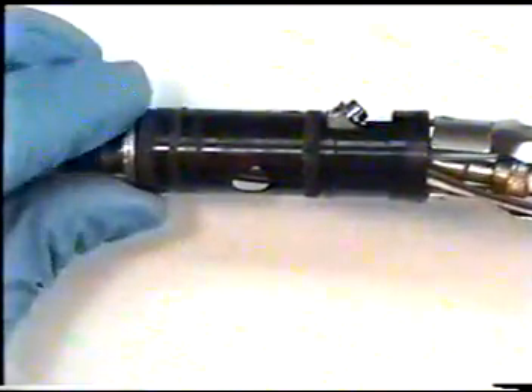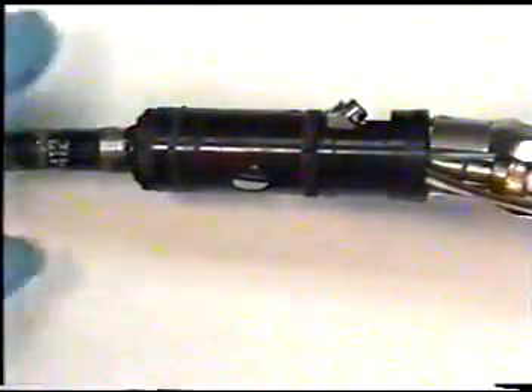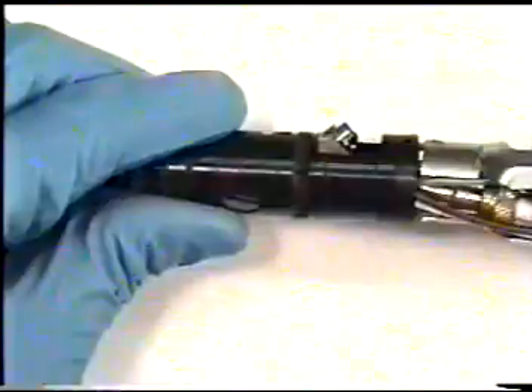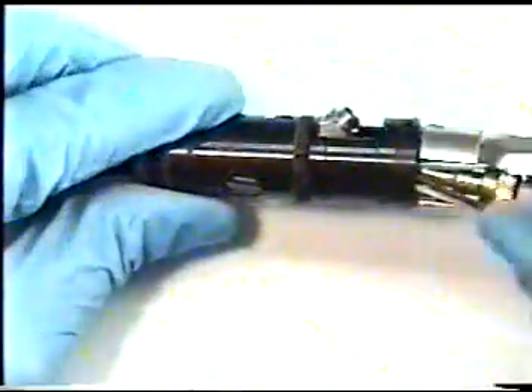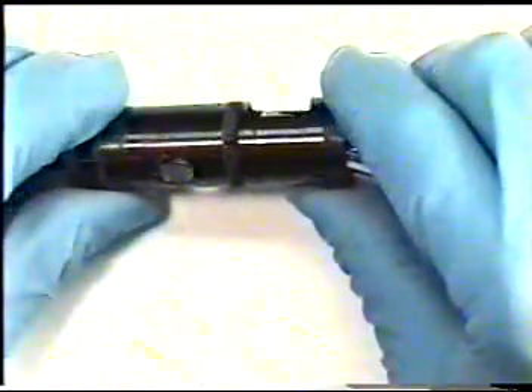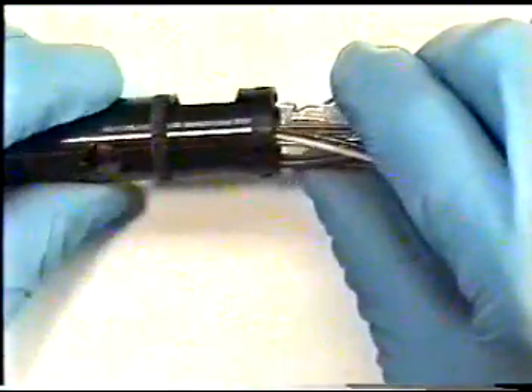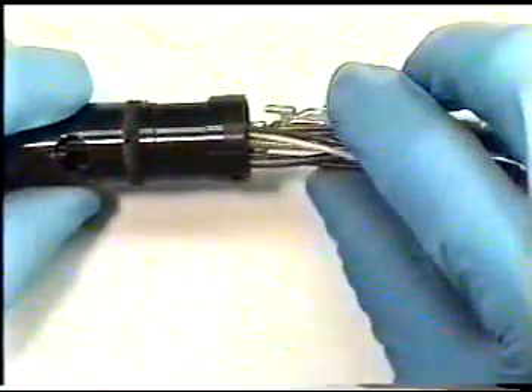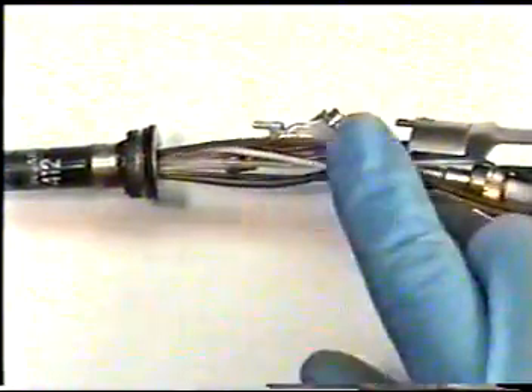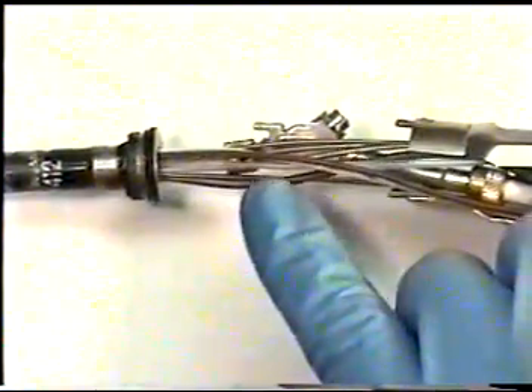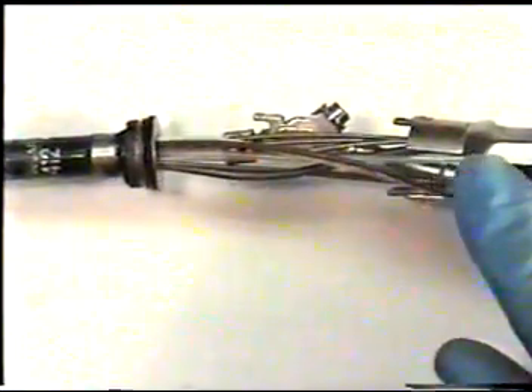Fully remove locking ring from insertion tube to body control section. Very carefully slide off your black body control section piece over and down the insertion tube to meet your body cover. Being very careful not to pinch any of the wires, tubes, or light guide bundles, or image bundle, or CCD wire.